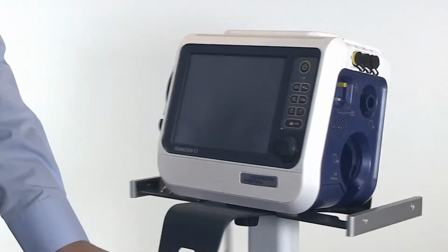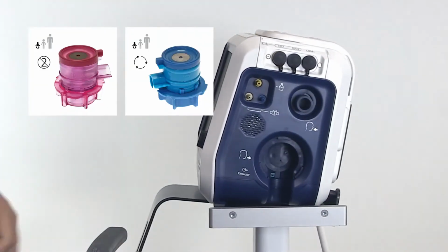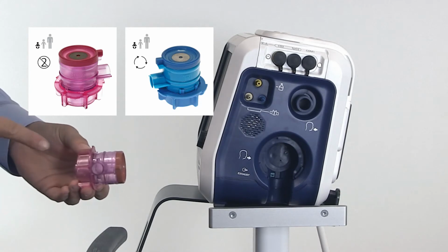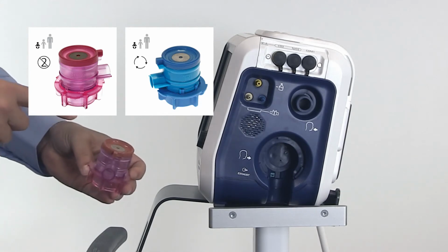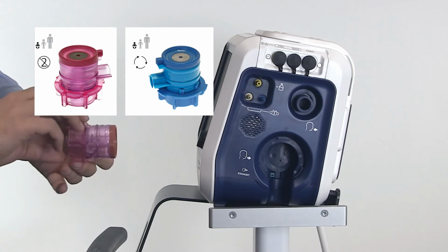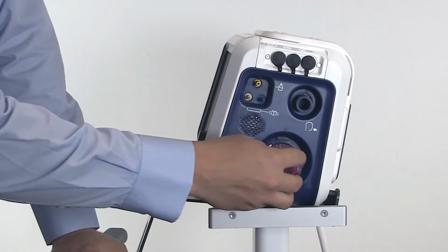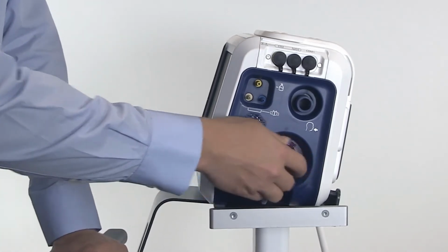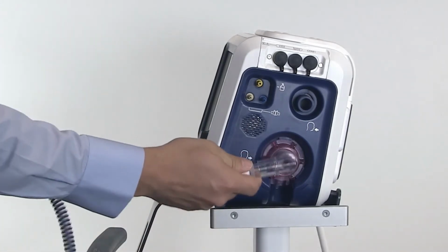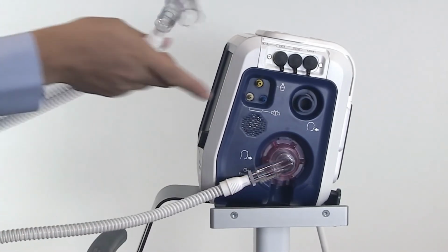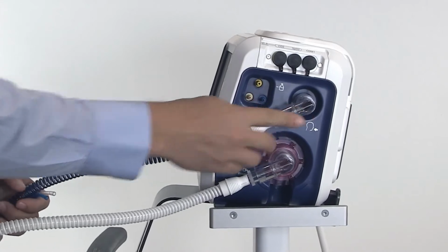Make sure you are using a dedicated neonatal expiratory valve, which has the same membrane as the other valves but a smaller internal diameter. Insert the neonatal expiratory valve. Connect the inspiratory and expiratory limb of the neonatal breathing circuit to the device.